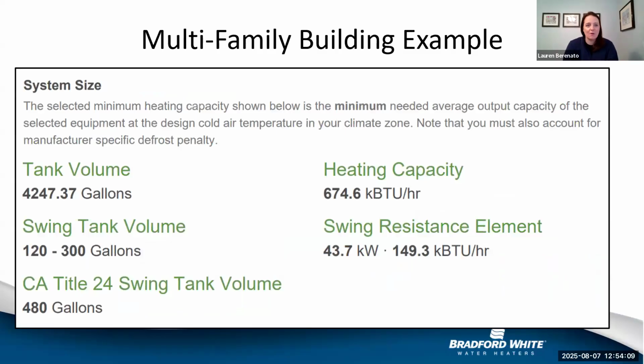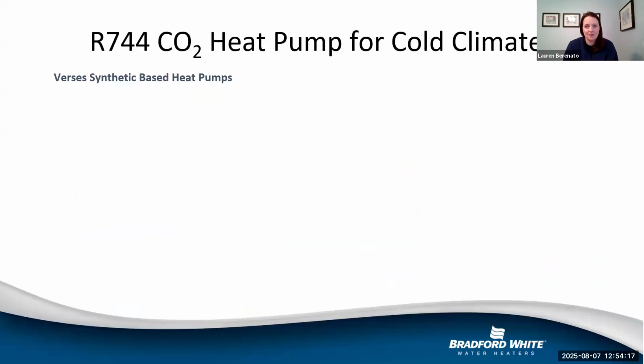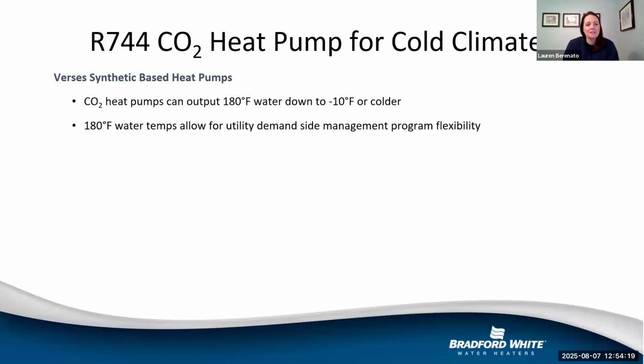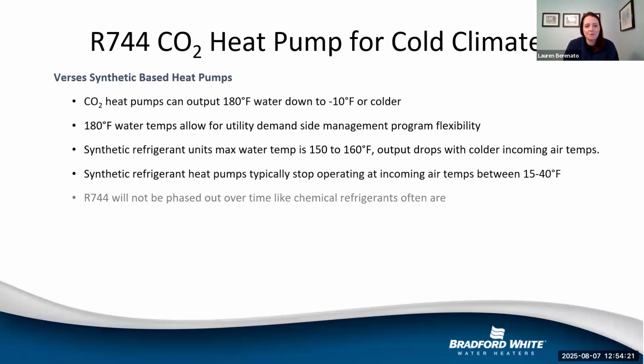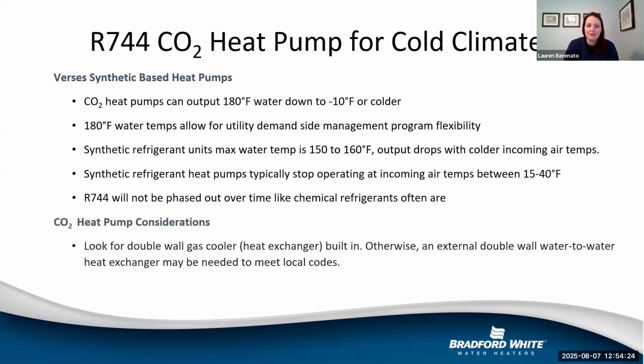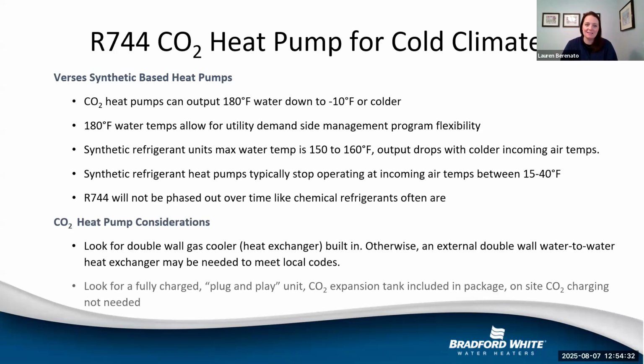This is just kind of going through that multifamily building example. It's just showing the tank volume, the swing tank volume, the different heating capacities, as well as the swing resistance element. So for CO2 units for cold climates, one of the things that is nice about this is that you can store your water at a higher temperature, all the way up to 180 degrees Fahrenheit. Now, that is not always best practice, as it will likely be too hard on the materials that it's coming in contact with from your line.